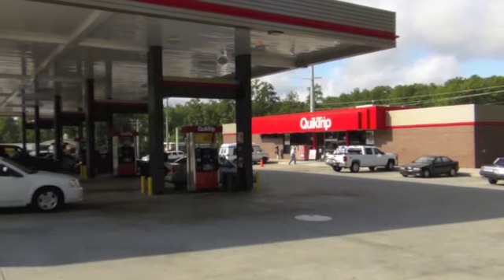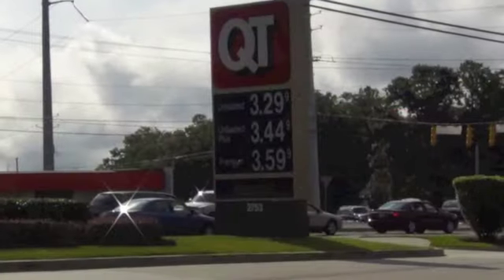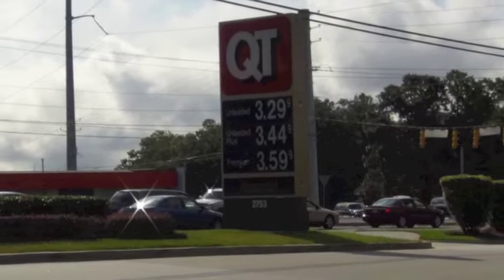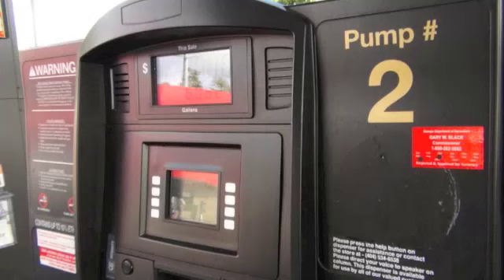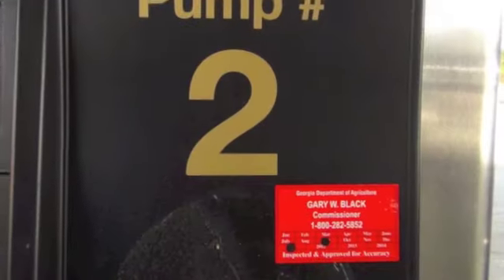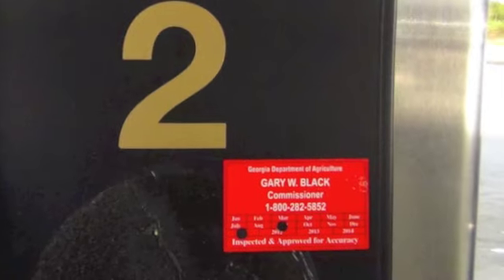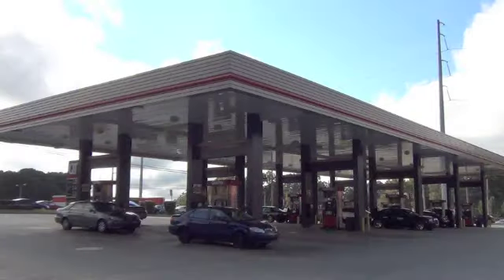Basically, what our inspectors are looking for in an inspection like this is where we check each pump to make sure it's pumping accurately. We do a 5-gallon test to check the calibration. We also are pulling samples of the gas to make sure that the octane rating is accurate. We make sure that the ethanol content is okay. And we're checking also the advertising to make sure that it's accurate, not deceptive or misleading in any way. Basically, we're just making sure that the consumer is getting what he's paying for at the pump.